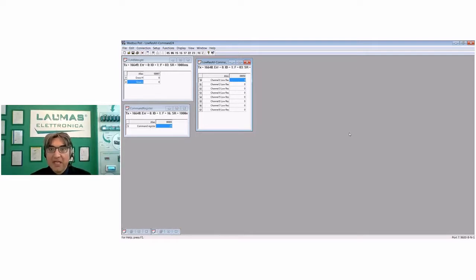Here I have the same setup that we have used for the videos. So there is a telemate connected to the usual 6 load cell platform. I have connected the telemate via RS485 to my laptop using a USB to RS485 converter. And I'm using a software called Modbus Poll, which can also be tried for free if you are interested in it. And this acts as a Modbus master, whereas the telemate is a Modbus slave. So I'm sending queries to the telemate and getting answers.